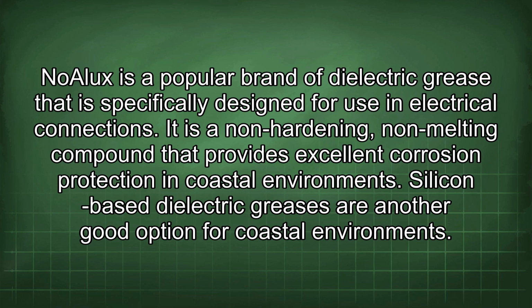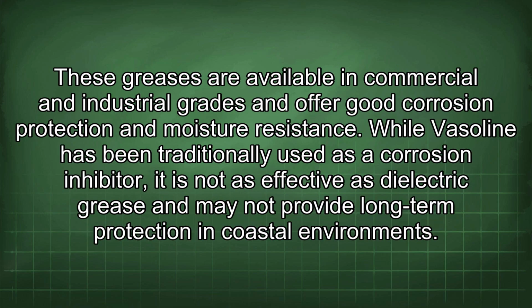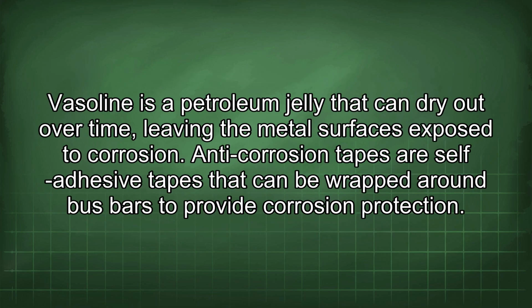Silicon-based dielectric greases are another good option for coastal environments. These greases are available in commercial and industrial grades and offer good corrosion protection and moisture resistance. While Vaseline has been traditionally used as a corrosion inhibitor, it is not as effective as dielectric grease and may not provide long-term protection in coastal environments. Vaseline is a petroleum jelly that can dry out over time, leaving the metal surfaces exposed to corrosion.